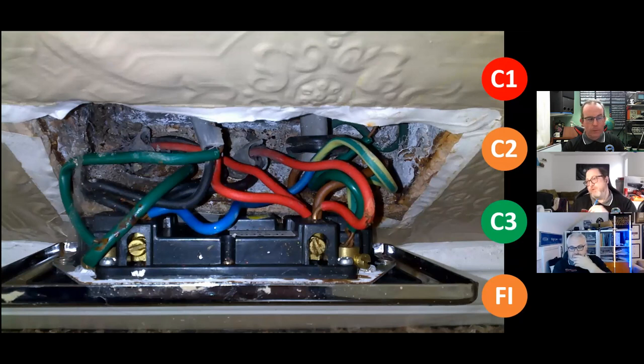I've also seen it before where people would take a spur from a socket and then they'd actually bring another cable back and they'd actually connect a ring from that spur. And so then all of those extra cables will be putting a lot of loading in. So you need to look at the loading on that circuit.